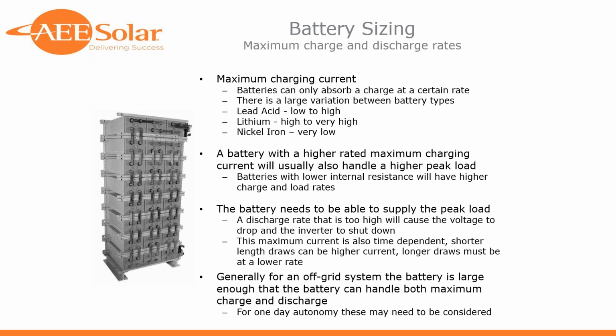Unfortunately, most of the inverters and charge controllers we have can be set to charge only at a certain rate, but if you're grid tied, you don't want to be limiting the amount of energy that you send into the grid tie system. And separating those two has not really been part of what any of the manufacturers have done to date. So you do have to look at this parameter, and size the battery such that it will absorb the full charge of the solar array, particularly in a backup system.